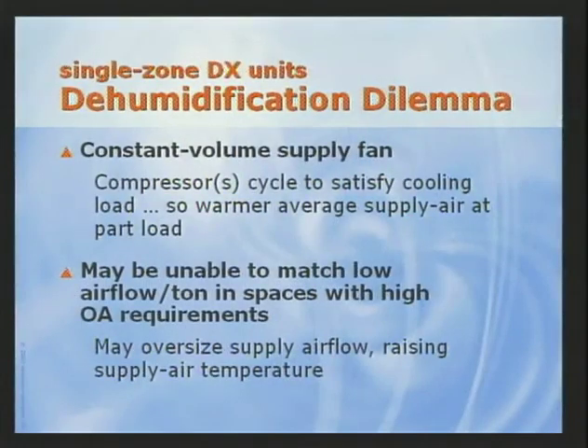However, this outdoor air is not part of the space sensible load, so supply airflow, or CFM, required is typically unaffected. For a given space load, an increase in the ventilation load requires a unit that can provide more capacity, or tons, at the same airflow, so a lower CFM per ton. Now, packaged DX equipment typically has a limited range of CFM per ton. Selecting a larger piece of equipment to provide the additional tons can often yield a higher than necessary supply airflow. Oversized supply airflow means a warmer supply air temperature and less dehumidification. In non-arid climates, the result is elevated space humidity levels, even at full load.